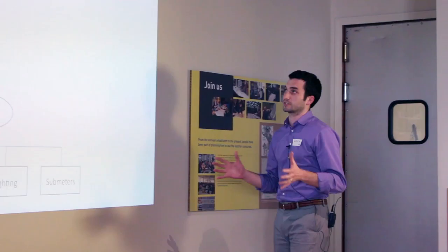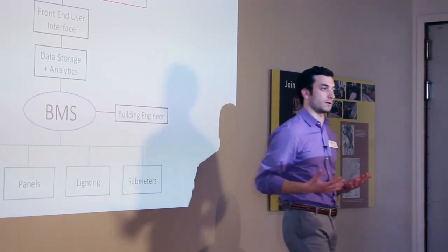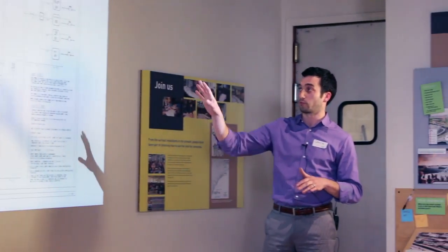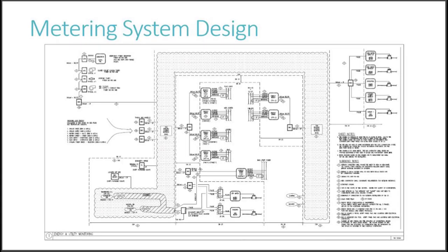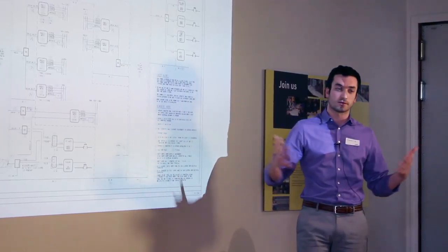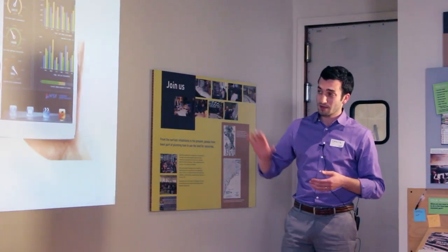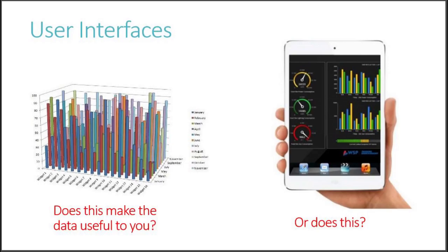What we're proposing is an optimized data collection system that takes all that information and puts it in the building management system where the building engineer can operate with it. We add data storage and analytics and produce a front-end user interface for different stakeholders. This requires integrated design — your electrical engineer, mechanical engineer, and controls contractor all have to pull together, as shown in this metering diagram from a project we worked on, so all the information is collated in a way that makes sense.